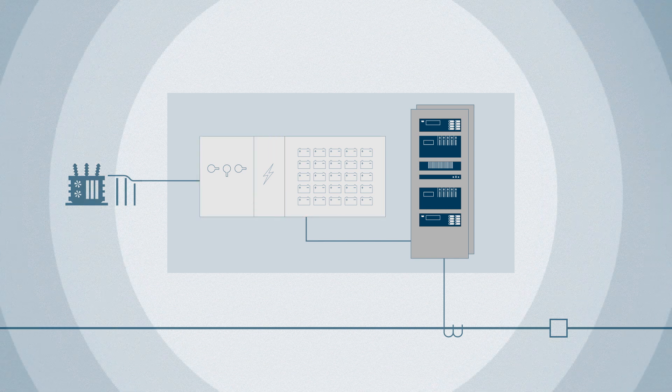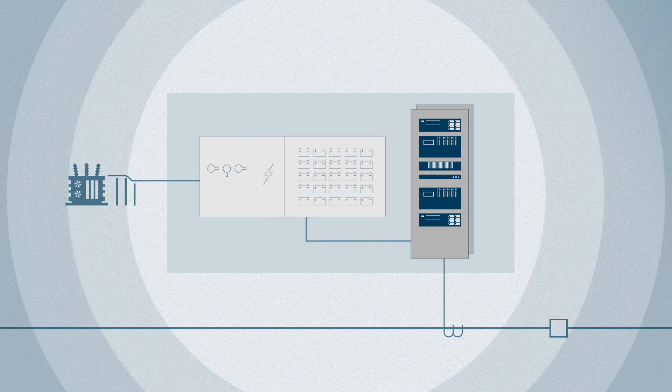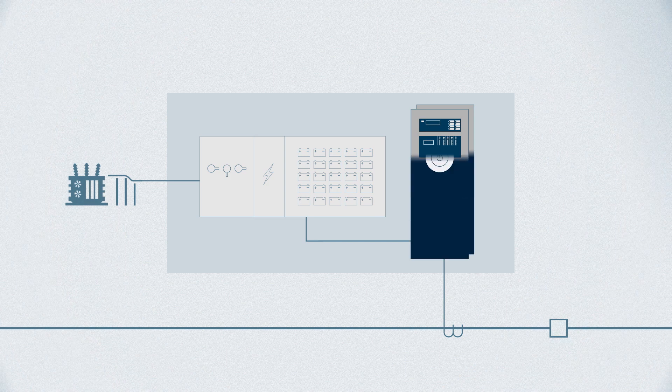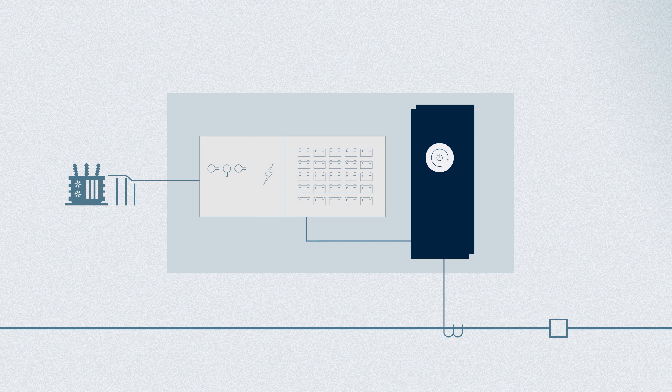A momentary interruption or voltage sag in the DC supply system can cause protection and control equipment to shut down, leaving critical equipment vulnerable and unprotected while those devices restart.